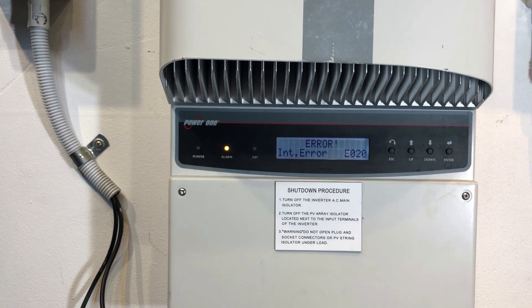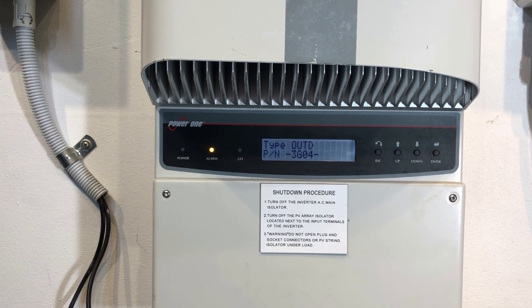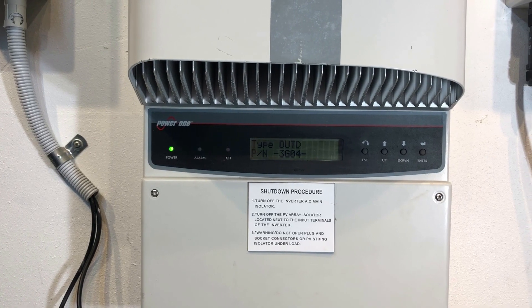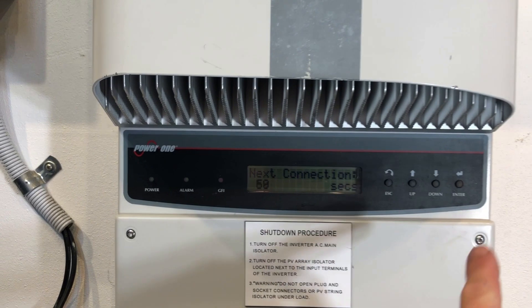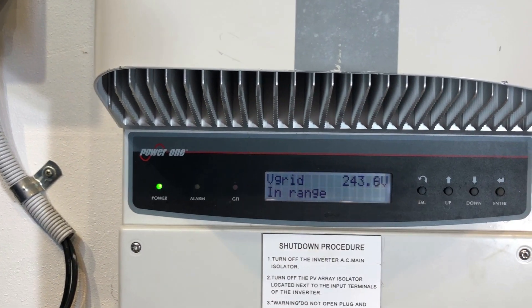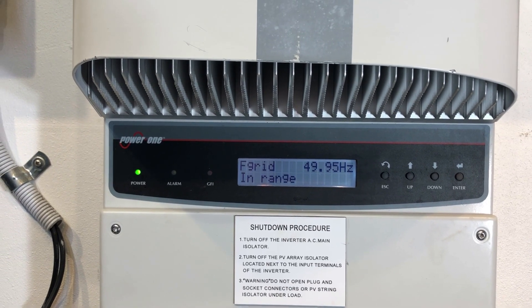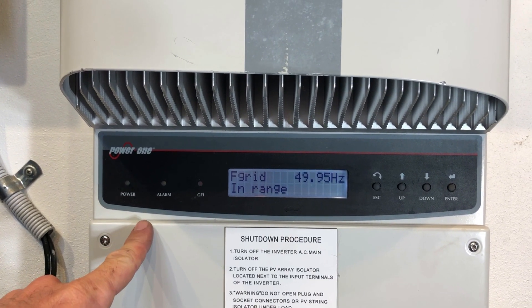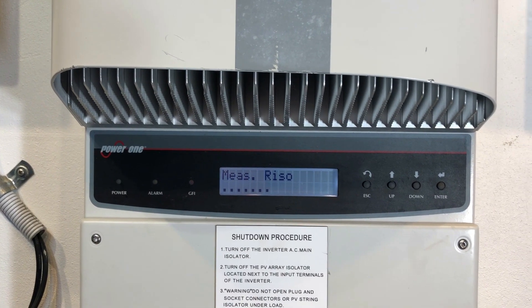Internal error E020 on an Aurora Inverter like this means that there's a problem with the DC-DC relay inside the inverter. So there's an internal fault with the system, and you can see after it's shown that error, the green light is now flashing, the alarm light has gone away, and it's now attempting to reboot the system.